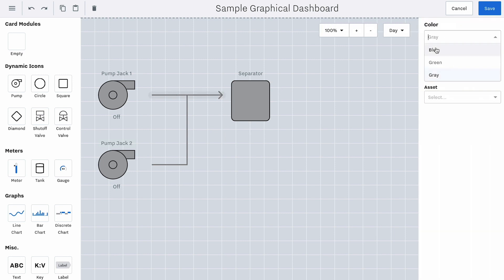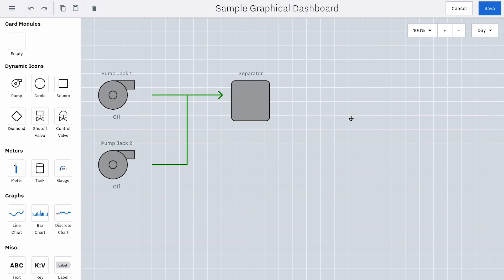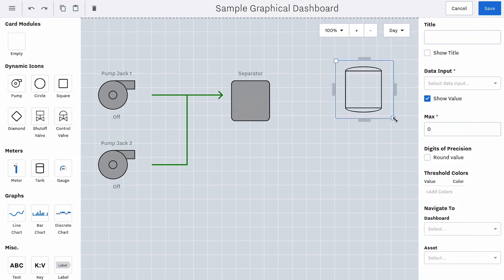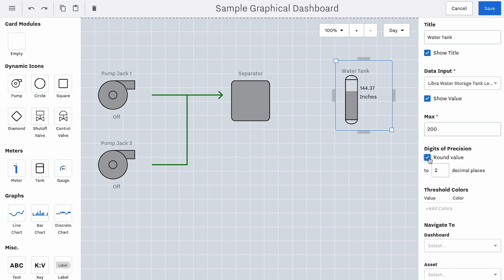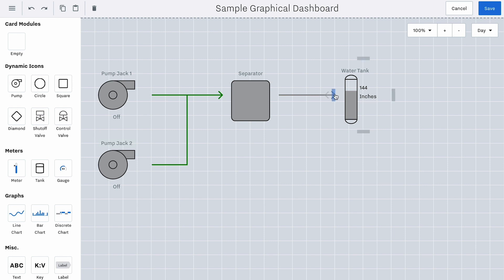Click into a line to configure the color and whether or not it has an arrow. You can use a meter icon to display values in relation to maximums that you set. For example, you can create a tank associated with a data input for tank level. Drag and drop a tank in, create a title, select a data input, and set a maximum. This maximum will determine the virtual tank fill level based on its current value. For example, if the maximum is 200 and the tank level is currently at 100, it will look half full. You can also add numeric thresholds that will change the color of the tank fill, or simply set it to standard gray.